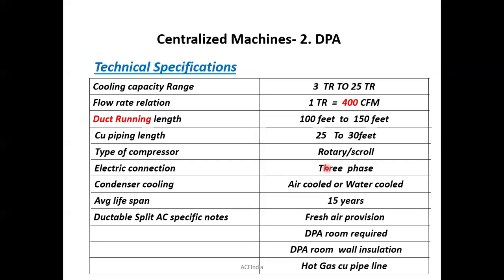Okay, now the other technical specifications are the same, which means the copper piping length, that is compressor to condenser and condenser to indoor unit. The compressor should be rotary or scroll, and it should use a three-phase electrical connection. And the condenser cooling should be either air cooled or water cooled. Then the important major things are that a DPA room is mandatory and DPA room wall insulation is also mandatory. And for that DPA room, you need to provide the fresh air connections also. Then only a proper fresh air and return air mix-up will happen. All right, so is the idea clear? Okay, so this is all about this one.